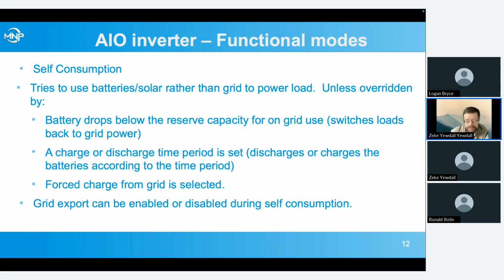Another thing to realize is that grid export can be enabled or disabled during self-consumption. A lot of older inverters, if you did a self-consumption setup, which was usually called a high battery transfer or a low battery transfer, depending on the terminology they used, would operate from the batteries until they got down to a certain point, and you usually could not sell to the grid.